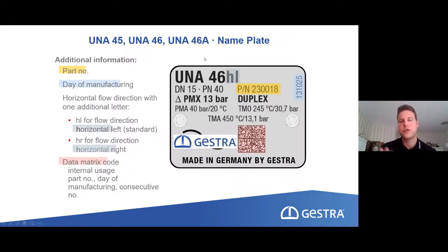Each and every steam trap has a nameplate attached, and sometimes we don't really know what we have inside here, but by the nameplate we can figure that out very easily. If we have a GESTRA ball float steam trap installed, then we are speaking about a so-called UNA. So it's a UNA ball float steam trap of the 4 series. So it's the new series that we have in operation.